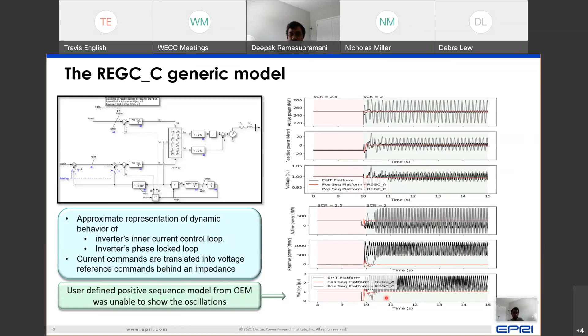Now, this model that we speak about, the REGC, because it is specifically designed for low short circuit environments, and because it can provide this good picture in low short circuit environments, it can equally be tuned well to operate in a short circuit ratio of 0, or a grid forming representation. So as this example, you can see that when you compare a PSCAD grid forming behavior versus a representation in PSLF and PSSE, which are the positive sequence tools, you can see that there is a good representation of the trend of the response if a system islanding event occurred at time equal to 5 seconds.